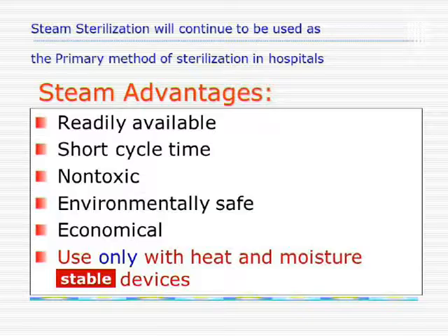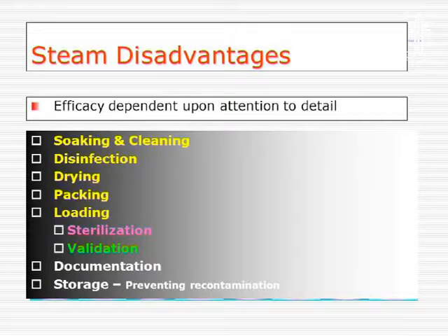The advantages of steam sterilization are that it's readily available, not very expensive, and non-toxic. The only limitation is that only heat-stable items can be autoclaved. Efficacy depends not just on autoclaving, but on how you clean and disinfect the instrument — reducing the bioburden from 100 million to 1 million makes the process easier. Packing, drying, and loading are all important, and you'll see these practically in the video following this.